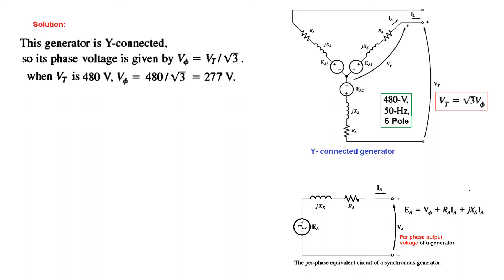The generator is Y-connected, so we take a single phase. The phase voltage is V-phi = V-terminal / √3. The line voltage is 480 V, therefore 480 / √3 = 277 V. So the phase voltage is 277 V.